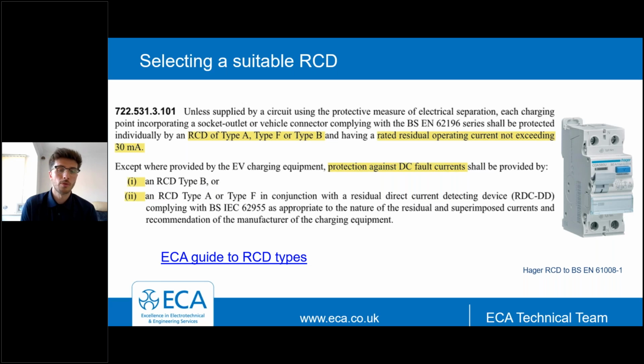And we'll go into that in a bit more depth in a moment. Now, the things I want to highlight at the moment, though, is the RCD type. So this regulation is clear that the RCD either needs to be a type A, type F, or type B, and it can't exceed 30 milliamps.